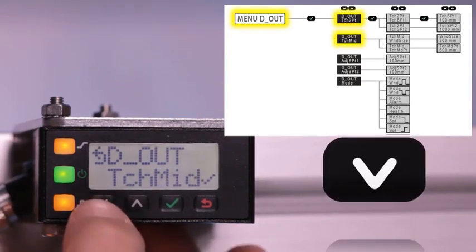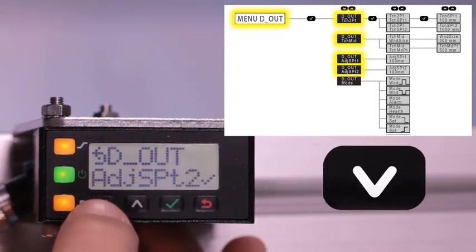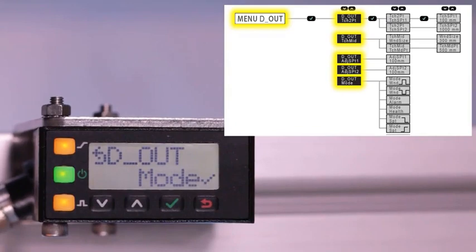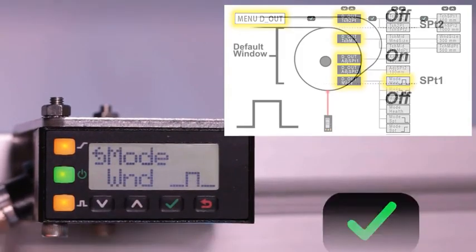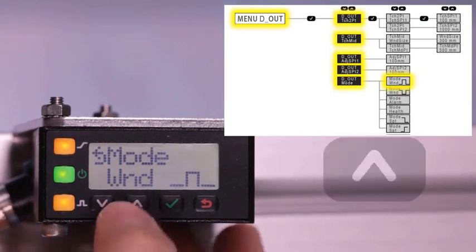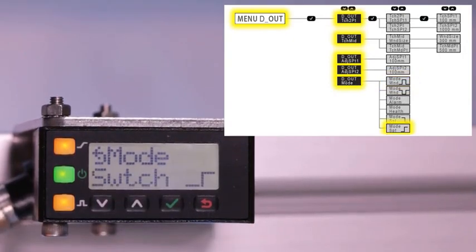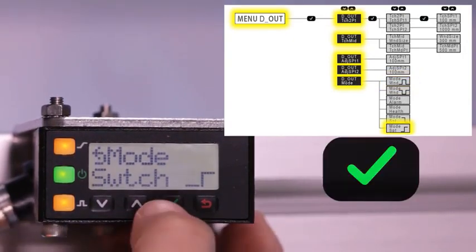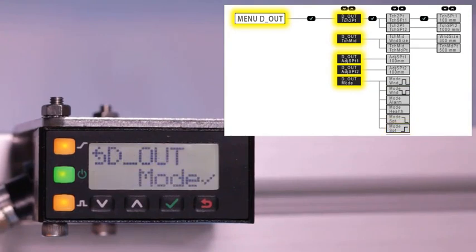Click down to cycle through the other options until getting to mode. Click enter to access the mode options. The default discrete output setting is a normally closed window where the output is on when a target is located between the two switch points. Click up to cycle through the different mode options until getting to the normally open switch point option and click enter to save this setting.